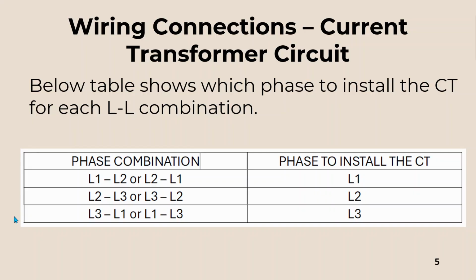To see that in the table, we go to line 1, line 3, or line 3, line 1. If the phase combination is line 1 and line 3, then you have to install the CT at line 3. Same case for the remaining combinations. If the load is line 1 and line 2, you have to install the CT in phase line 1. If the phases are line 2 and line 3, you have to install the CT in line 2.